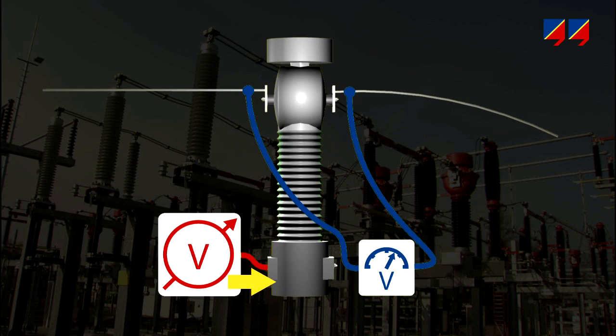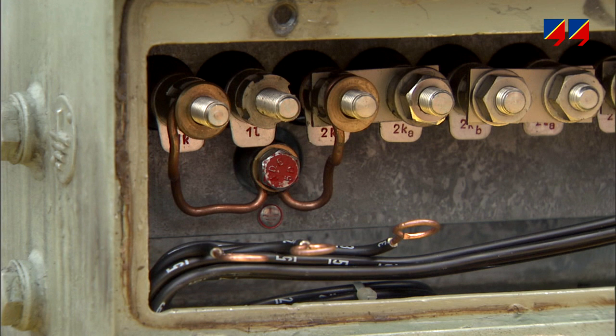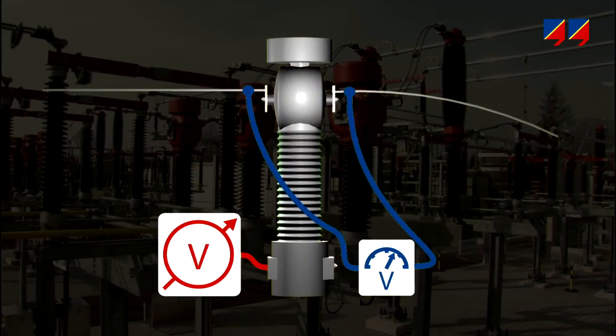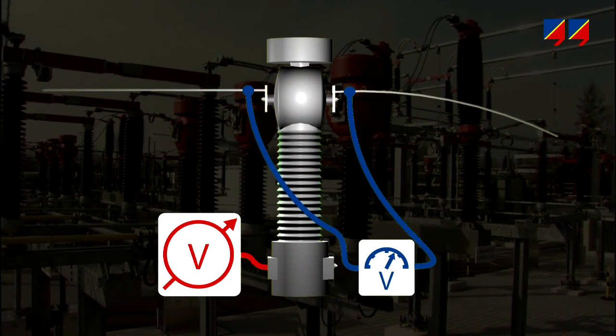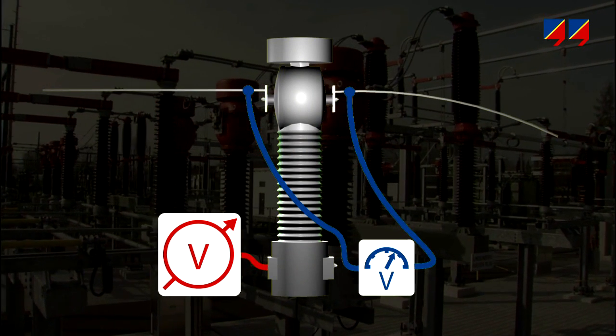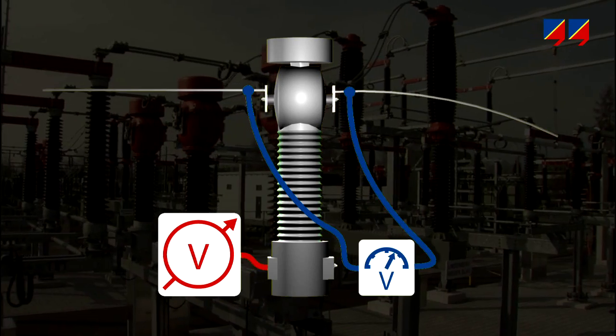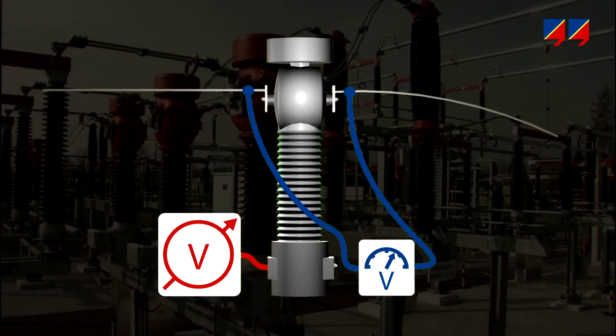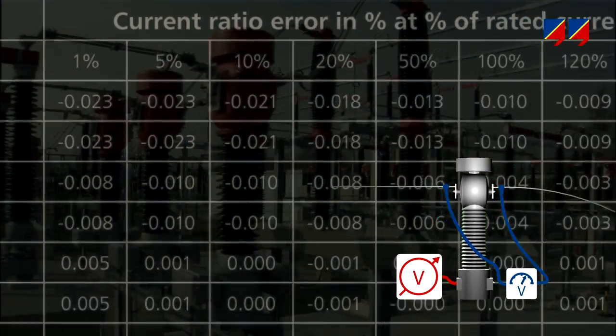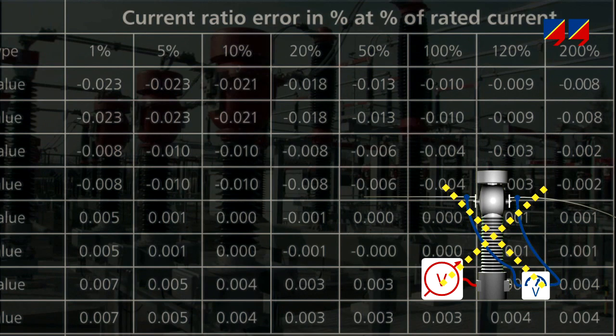Using a variac to inject voltage on the secondary side and measuring the voltage induced on the primary side allows confirmation that the protection or measurement circuit is connected to the correct CT core and tap. As it uses power system frequency, the method's accuracy is limited as it is directly influenced by external disturbances. In addition, it cannot measure a CT's accuracy at defined current and burden values.